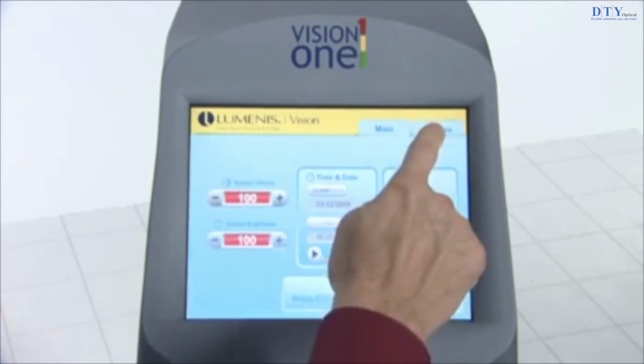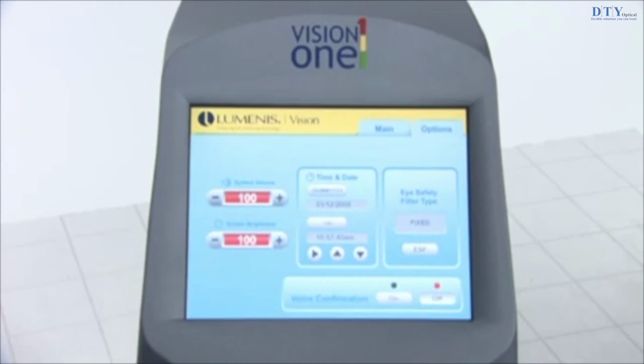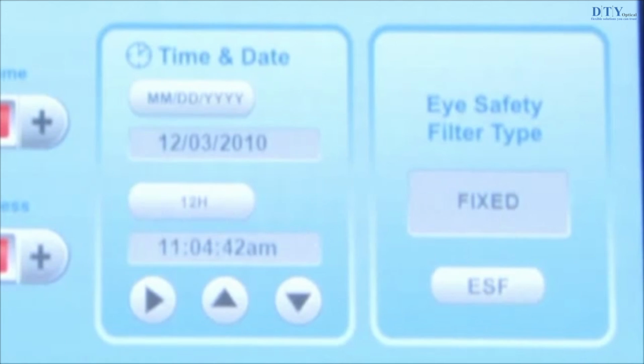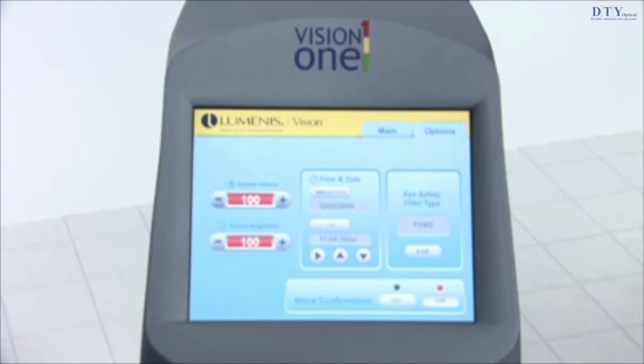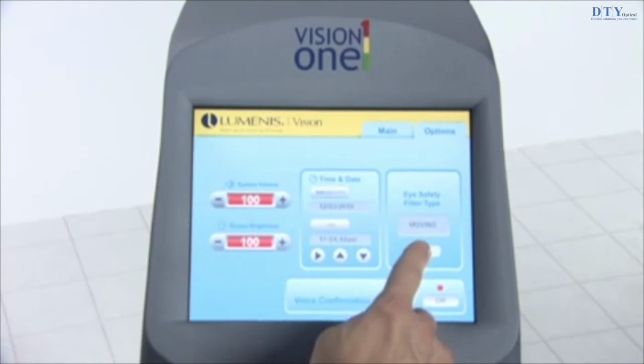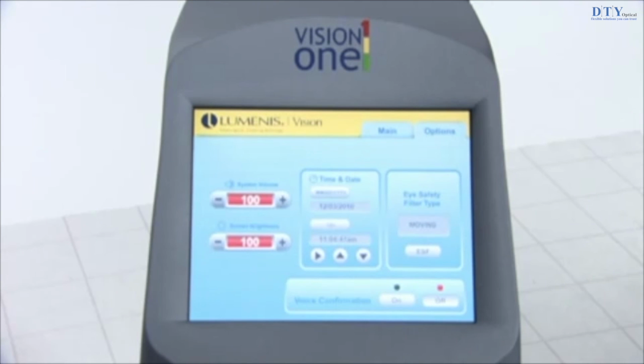System options, such as eye safety filter type, system volume, and screen brightness are selectable from the options screen. One or more of the following eye safety filter modes are available, depending on the type of foot switch, delivery devices, and eye safety filters that you have connected to the laser. Fixed. The eye safety filter is always in position. Moving. The eye safety filter moves into position when you depress the foot switch while the laser is in ready mode. This functionality is available only with automatic eye safety filters.